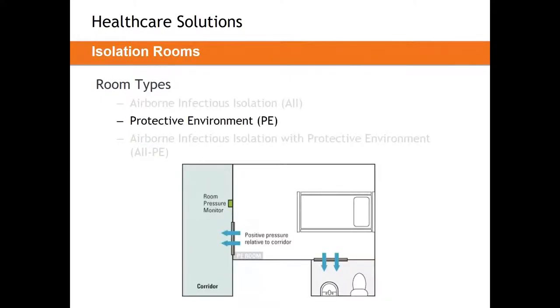The protective environment, or PE room, is essentially the opposite of the AII room. The patient has a compromised immune system and their body can't fight infections as well. We protect this person by positively pressurizing the space — we constantly blast air out of the room to ensure no air infiltrates in. You'll see a large proportion of that offset air flowing out around and underneath the doorway.